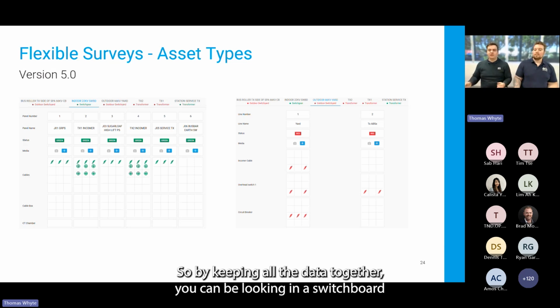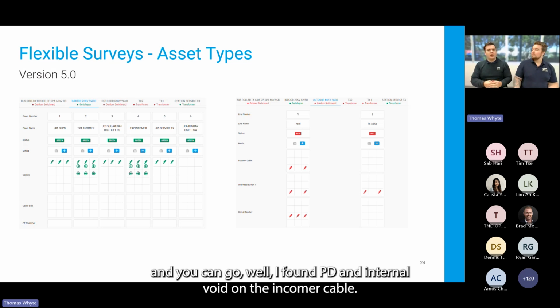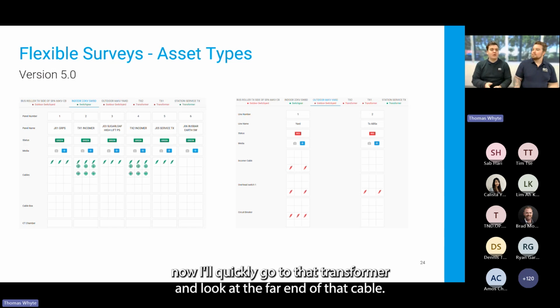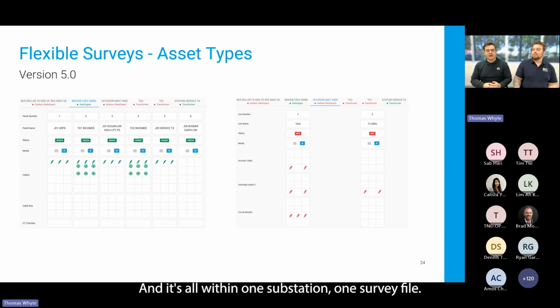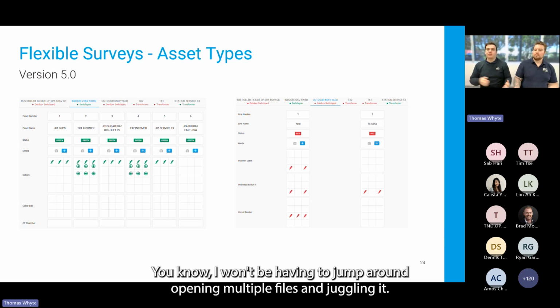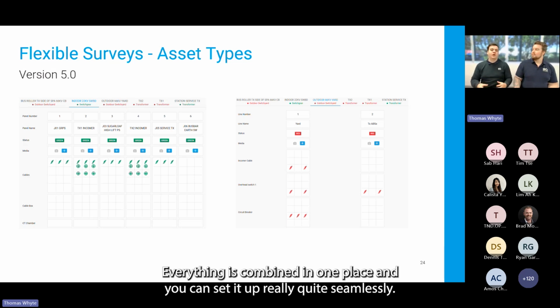So by keeping all the data together, you can be looking at a switchboard and think, well, I found PD, an internal void on the incomer cable. Now I'll quickly go to that transformer and look at the far end of that cable, and it's all within one substation, one survey file. You're no longer jumping around opening multiple files and juggling it - everything is combined in one place, and you can set it up really quite seamlessly.